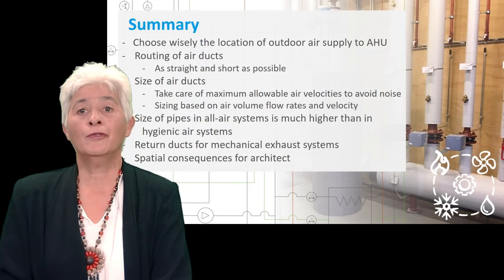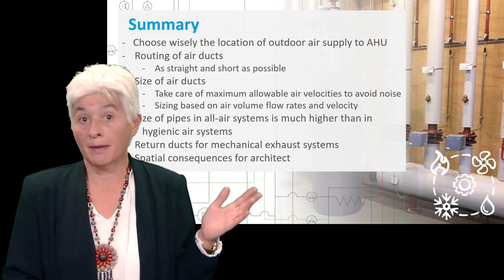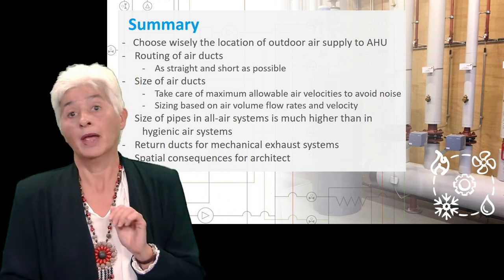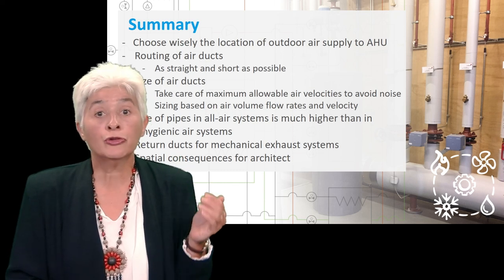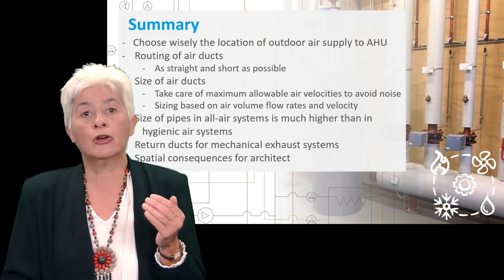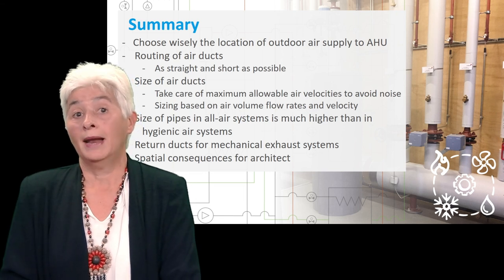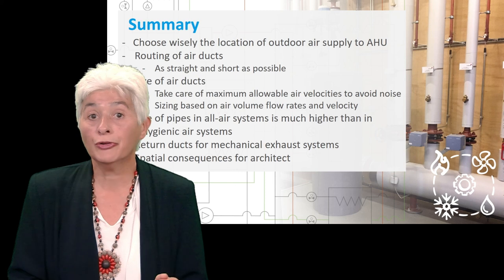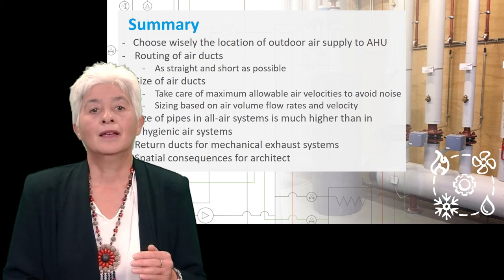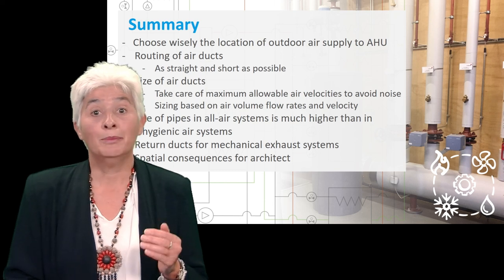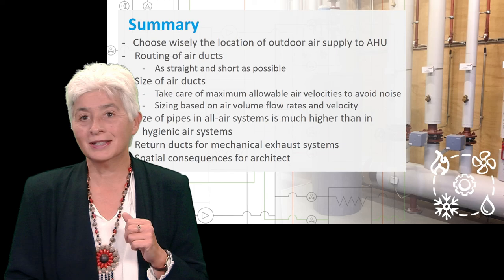In this lecture, you have learned where to place the outdoor air supply to the air handling units. You are also aware that when designing the routing of air pipes, it should be as straight and short as possible. As for the sizing of air ducts, it is of main importance to minimize the air velocity to avoid noise nuisance, and you have learned which formulas to use to size the ducts based on the needed volume flow rates. When all-air systems are applied, higher volume flow rates are needed to transport heat and cold, so generally the pipes are much larger than when only hygienic air is transported. Finally, don't forget the return pipes and be aware of the consequences of your design for the architect. That's something to discuss with her or him. Thank you for listening, goodbye!